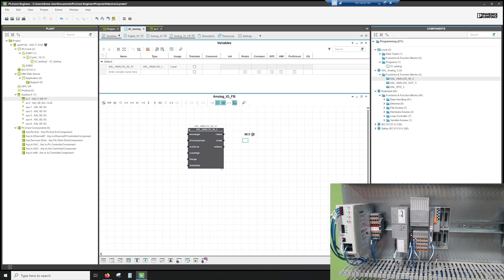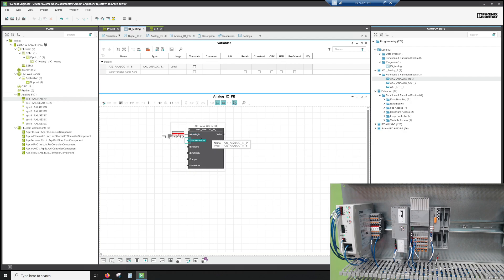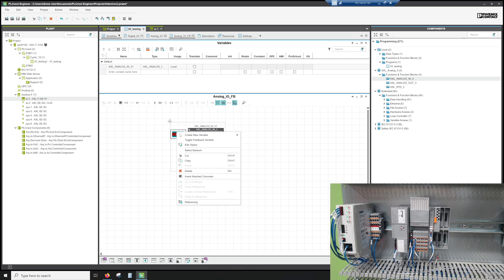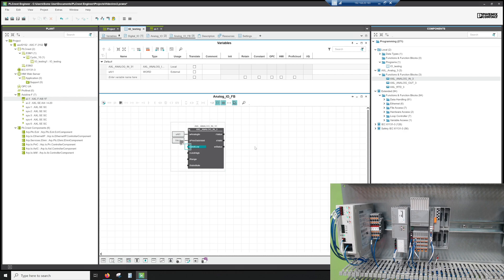Now that we're in the function block, we have the same parameters we just talked about. The word analog in is going to be attached to the card — we can call it something like E for external and AI1. Right-click, hit 'create new variable', make it an external variable, and it's already been added as a word, which is what we want. Since we don't have to worry about PROFINET validity, we'll just put true because the data will always be valid given that we are using the local bus.